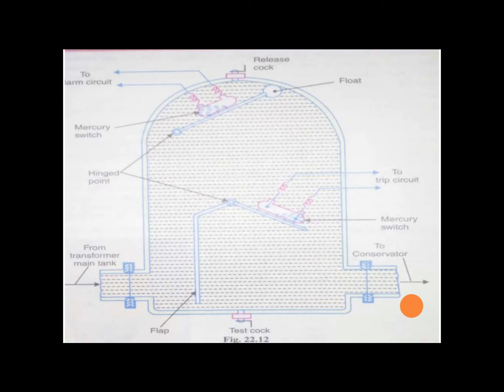When the gas is accumulated in the upper part of the housing, the oil level inside the housing falls. Due to which the hollow float tilts and closes the contacts of the mercury switch attached to it. This completes the alarm circuit to sound an alarm. Due to this, the operator knows that there is some incipient fault in the transformer. The transformer is disconnected and the gas sample is tested. The testing results give the indication what type of fault is started developing in the transformer.